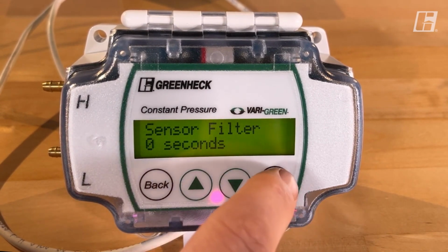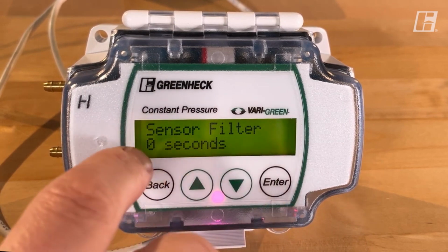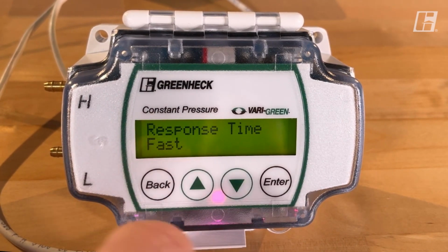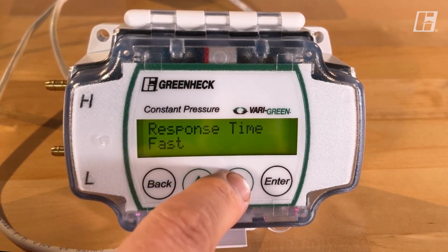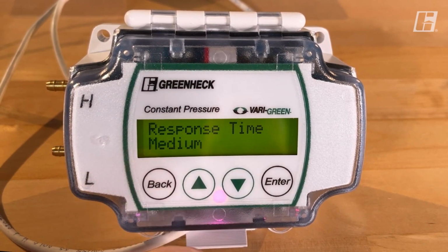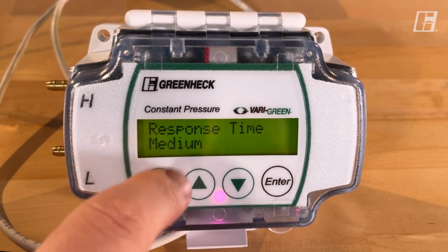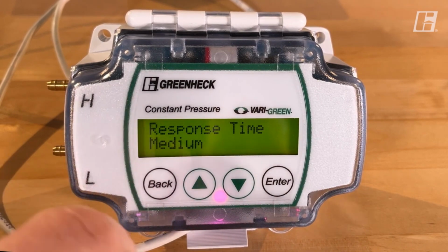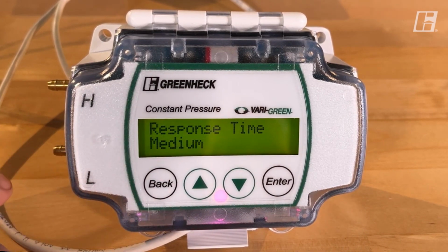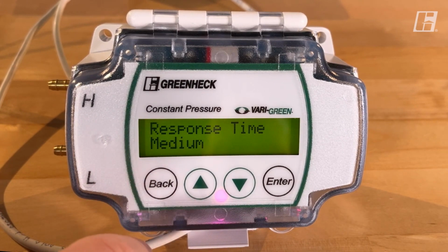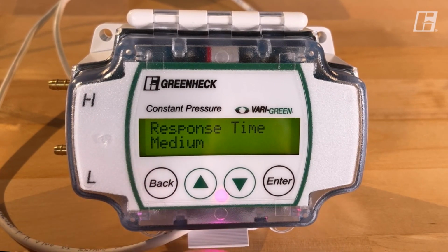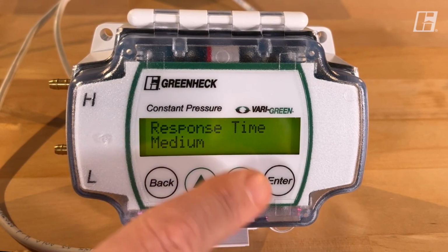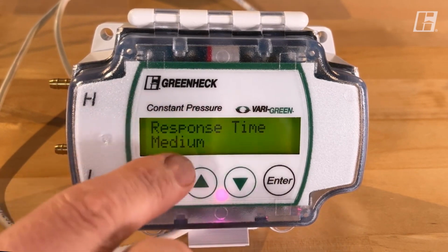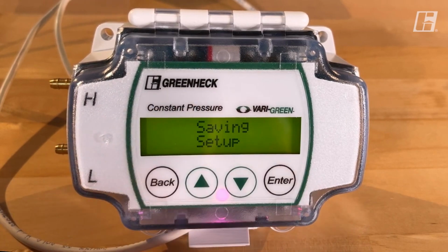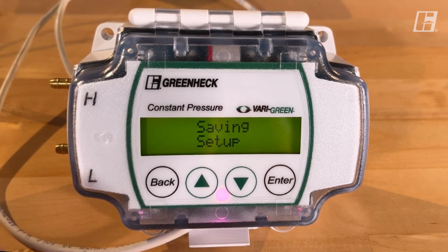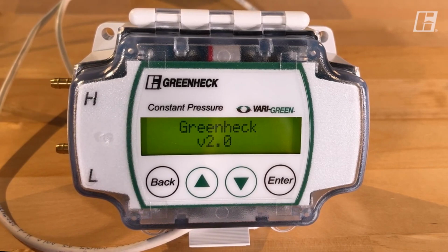Sensor filter, that has to do with the PID loop. Response time. Now you can set this as fast, slow, or medium. Medium is the most commonly used here, and basically you're changing how quick this can react to pressure changes. If it's too fast, you could find your fan ramping up and down for a long time trying to find the right speed. So you can slow the response time down. At this point, we're hitting saving settings, and this is programmed for our needs.